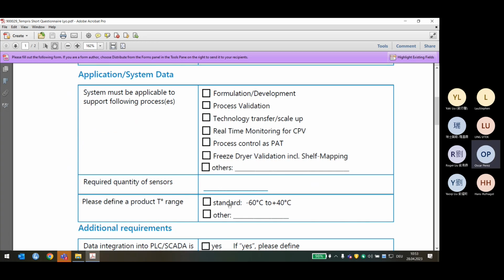How many sensors, and which calibration range? We didn't talk so much about it, but the standard that we are offering is -60 to +40. We calibrate our sensors under 6 measurement points. Accuracy, of course, I mentioned 0.7, but we can also offer -60 to 60 and -70 to 70. For lyophilization, these are the most common ranges that we offer. We have another solution for sterilization, where the range normally goes from 20 to 140 degrees.